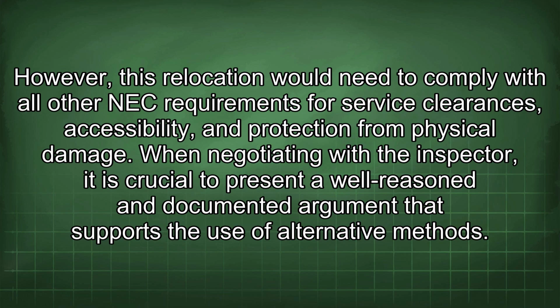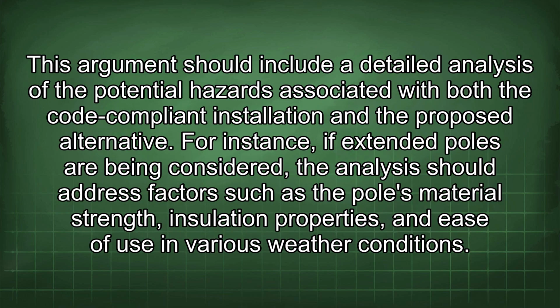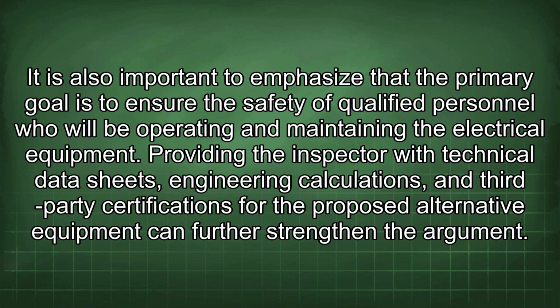When negotiating with the inspector, it is crucial to present a well-reasoned and documented argument supporting the use of alternative methods. This should include a detailed analysis of potential hazards associated with both the code-compliant installation and the proposed alternative. For instance, if extended poles are being considered, the analysis should address factors such as the pole's material strength, insulation properties, and ease of use in various weather conditions. It is also important to emphasize that the primary goal is to ensure the safety of qualified personnel operating and maintaining the electrical equipment.